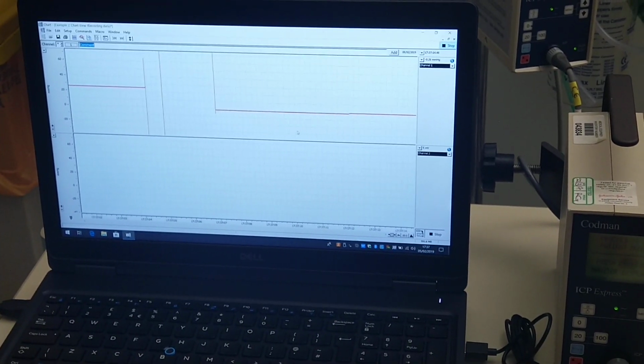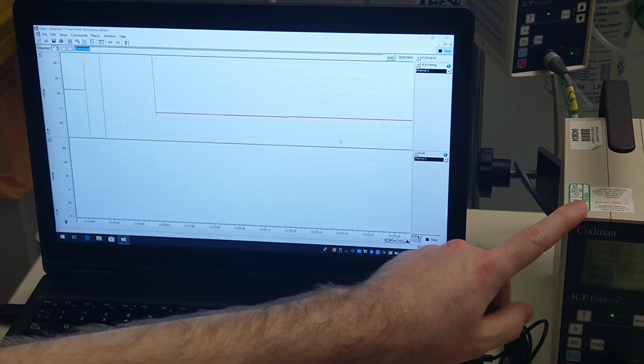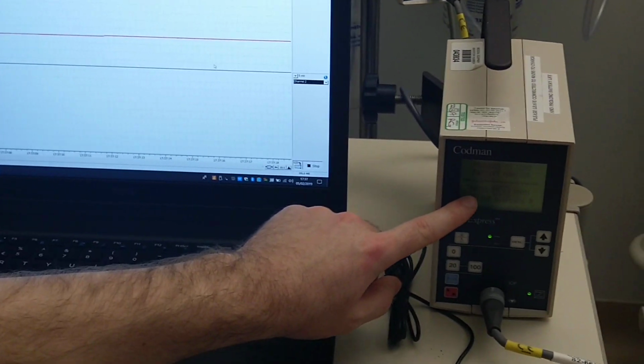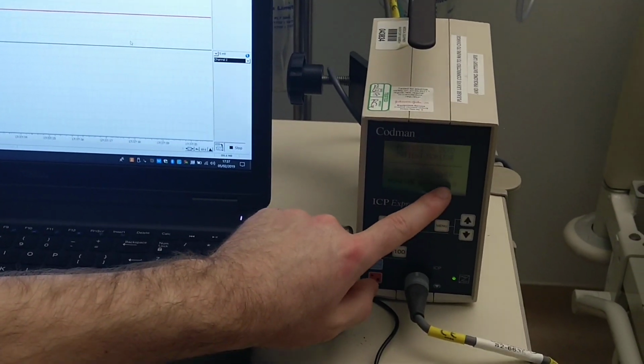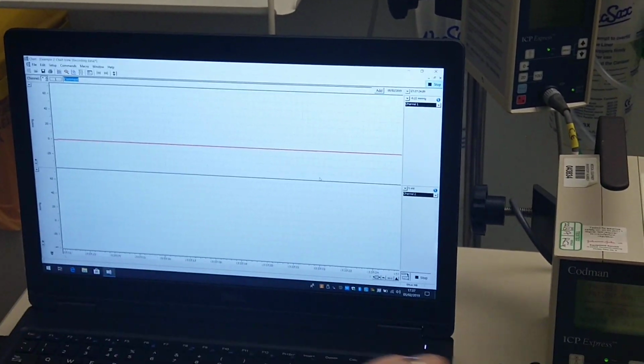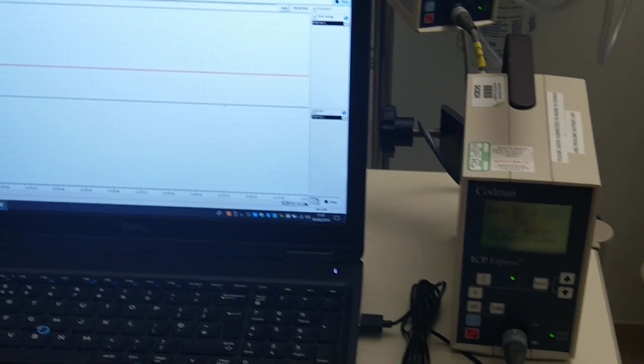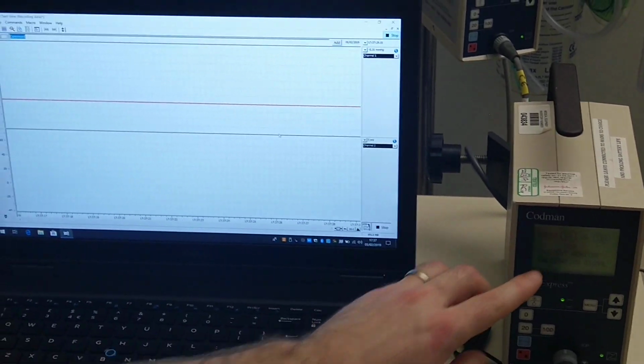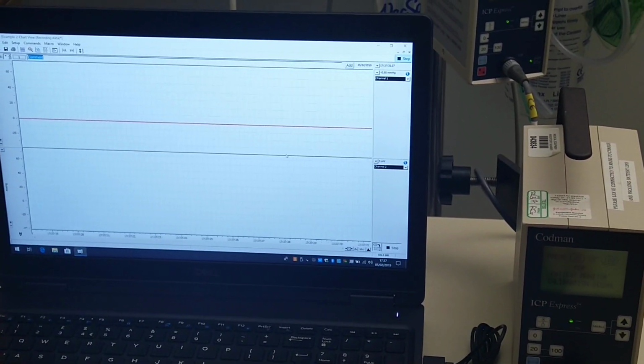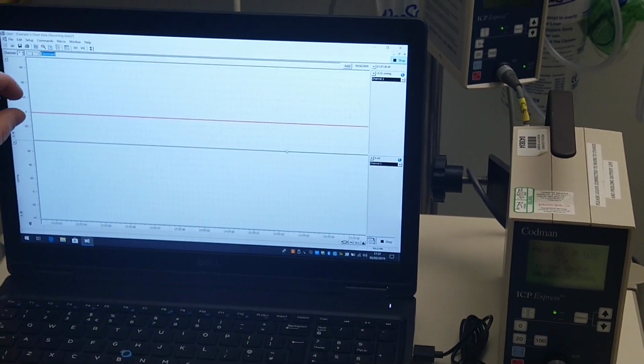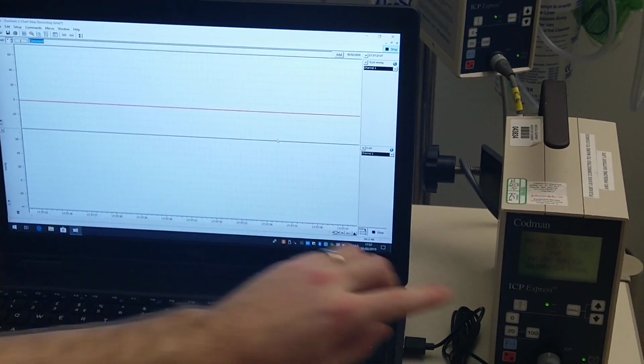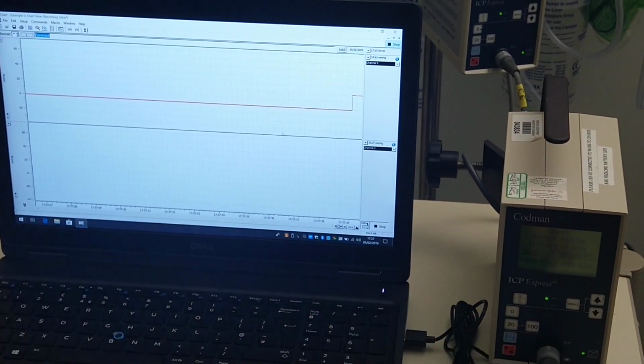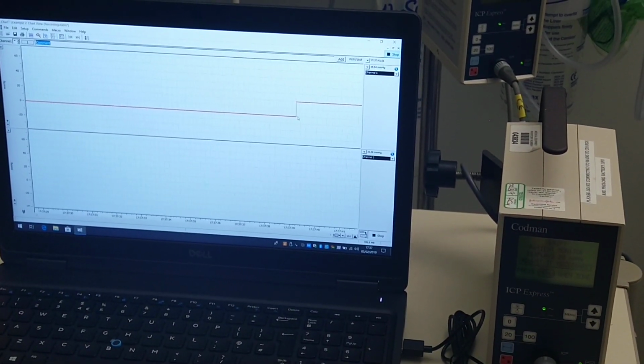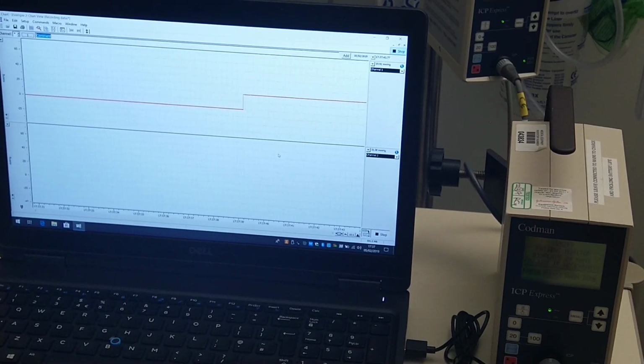Okay, so you can see if we look at the monitor, it says proceed to 0 patient monitor. Press menu when monitor displays 0. Currently it is displaying 0, so I'm going to press menu. Then it will ask you, press 20 for patient monitor calibration signal. So when I press 20 on here in a second, I expect to see this line jump up from 0 to 20 if it's properly calibrated. And as you can see, it's jumped from 0 to 20, so it's properly calibrated.